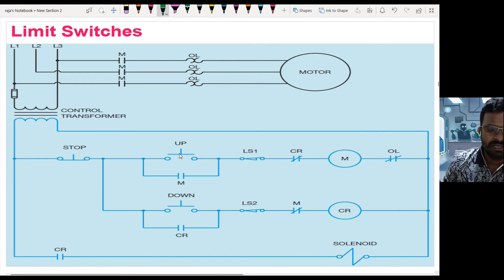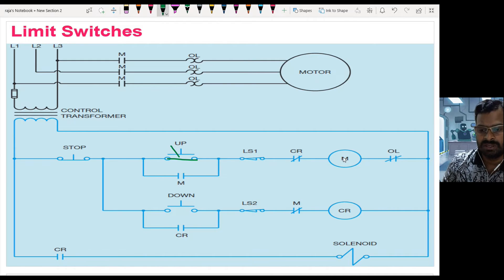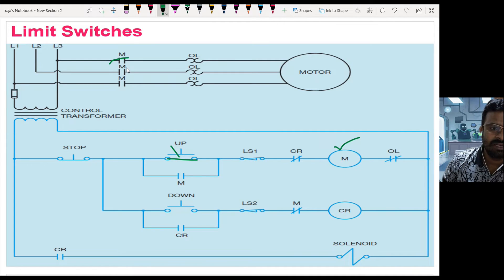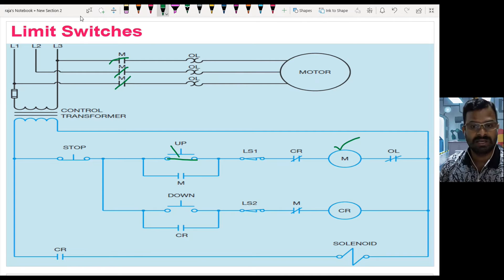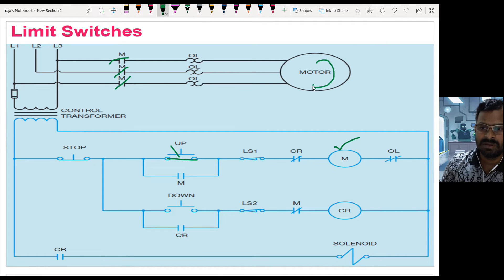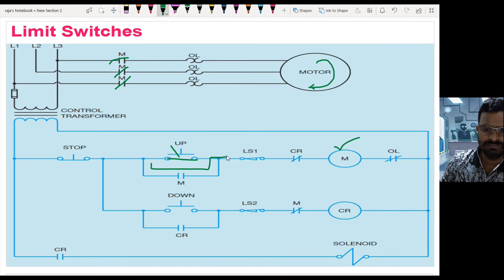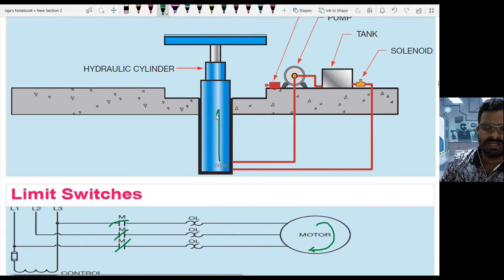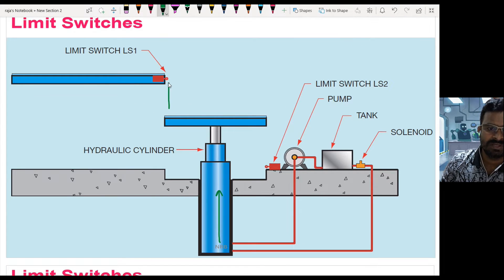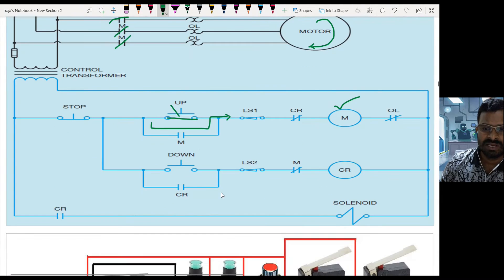If I close the start push button, the path is completed and current reaches the main contactor. When the main contactor is energized, its contacts close, and the motor coupled with the hydraulic pump starts working. The hydraulic pump pushes fluid to the cylinder in the upward direction, so the cylinder goes up until it touches limit switch LS1.